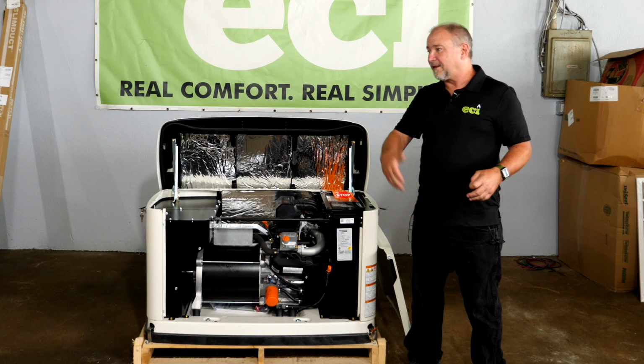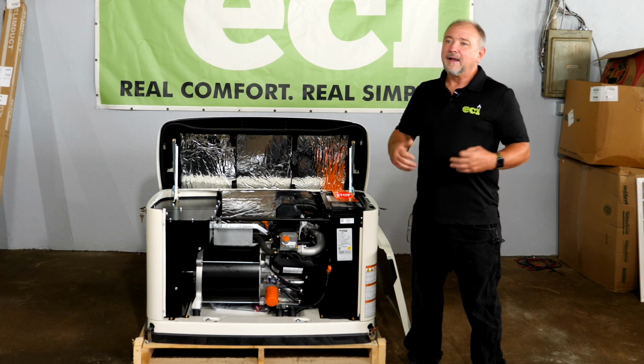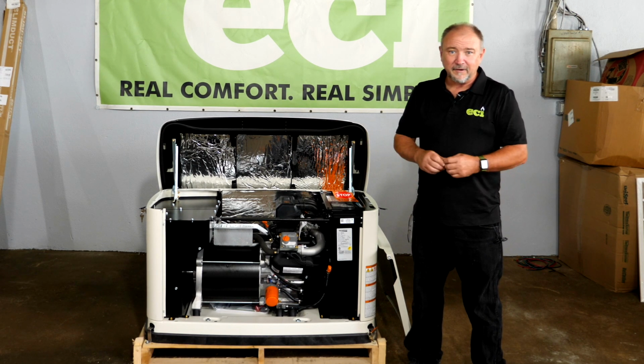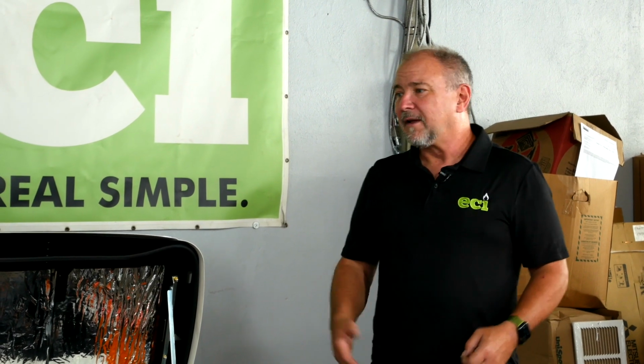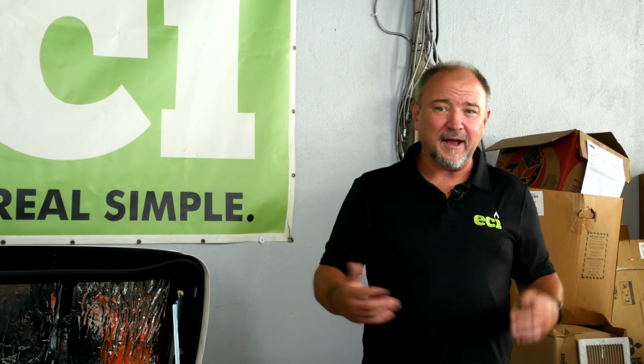If you lose power, I'll be honest, it's not instantaneous. Sometimes commercials fib a little, making it look like the power goes out and the generator kicks right on. There are actually time delays built in—power shuts down, and the generator waits to confirm it's not just a flicker, then starts up within a minute.